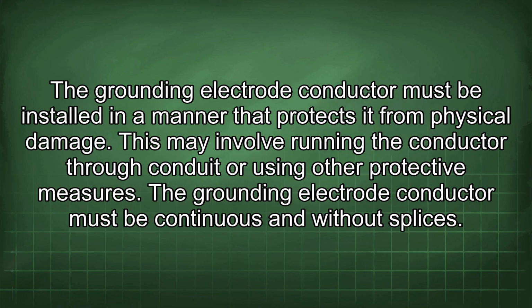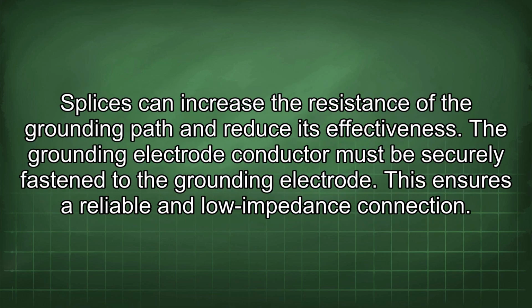The grounding electrode conductor must be installed in a manner that protects it from physical damage. This may involve running the conductor through conduit or using other protective measures. The grounding electrode conductor must be continuous and without splices. Splices can increase the resistance of the grounding path and reduce its effectiveness. The grounding electrode conductor must be securely fastened to the grounding electrode. This ensures a reliable and low impedance connection.